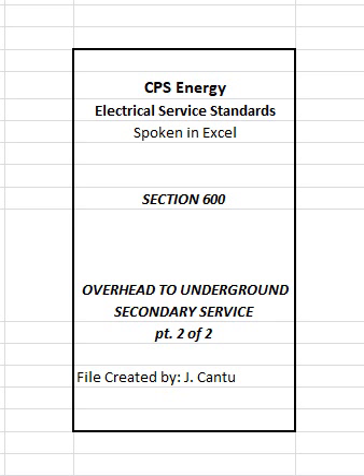Where CPS Energy approves such designs, customer shall be responsible for that portion of the service conduit, S, under the building or structure. Service conduits under the building or structure shall be installed as required to be considered outside of the building and shall terminate within 4 feet upon entering CPS Energy approved electric meter rooms. CPS Energy may require customer to install spare conduits and to locate meter rooms on exterior walls as close as possible to the transformer poles. Refer to definition of conductors considered outside of building.